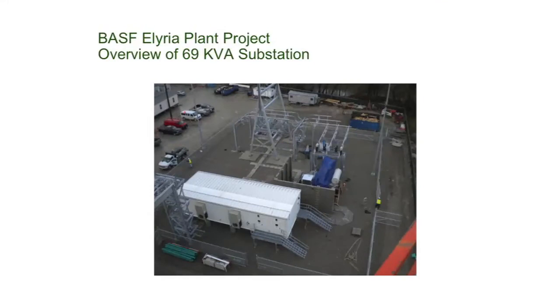Well, and the other thing is this building, they couldn't get it built to European specifications. European specifications would have said it would have had a false floor on it too, which would have added a couple more feet, and well, there's no way to get it underneath that railroad trestle. So they accepted the more traditional North American method of bottom cable entry in this case. So that's the main reason the building is sitting on piers instead of on grade, is to provide the bottom access to the medium voltage switchgear.